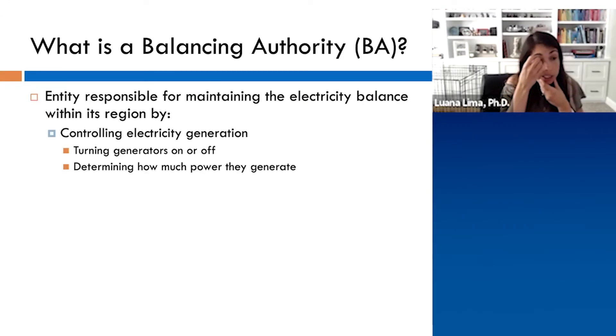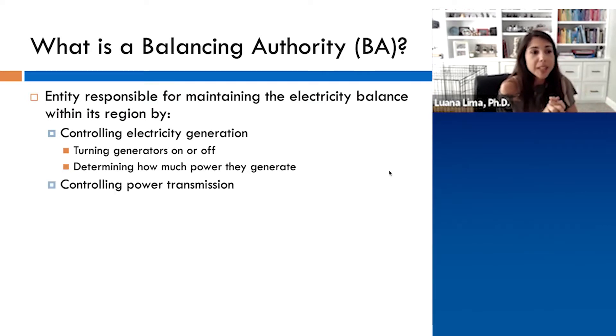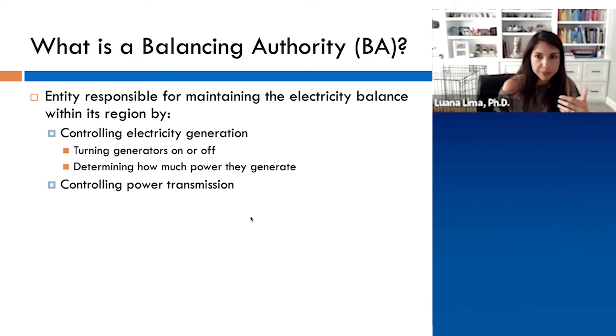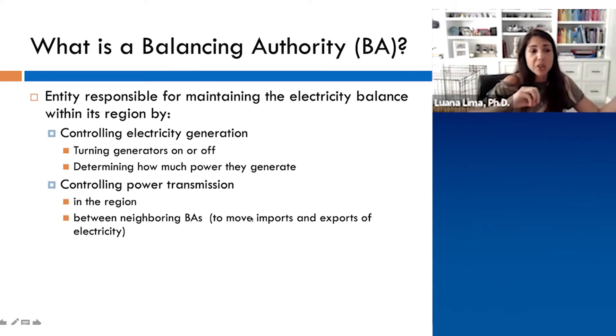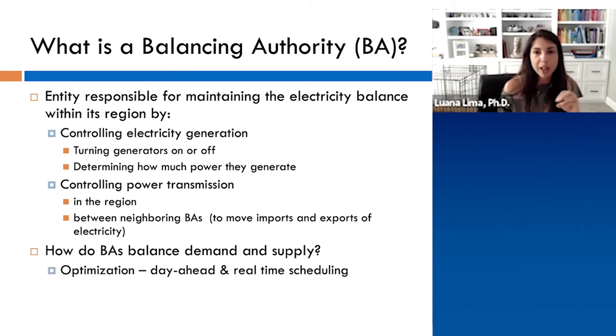I want to talk about the balancing authority perspective, specifically the optimization models used to find the dispatch for generators and to find the electricity prices traded on those markets. The balancing authorities are the entities responsible for maintaining balance within their regions. They control electricity generation, turning generators on and off, determining how much power they can generate, and they also control power transmission and interconnection with other balancing authorities. The key question is how they balance demand and supply at all times, and the answer is using optimization models.